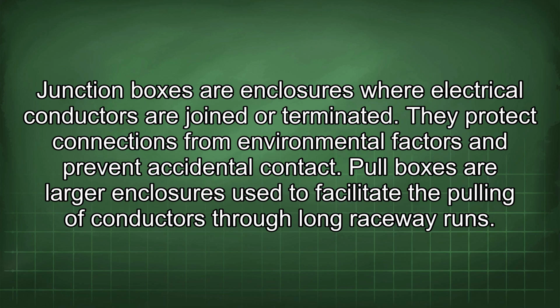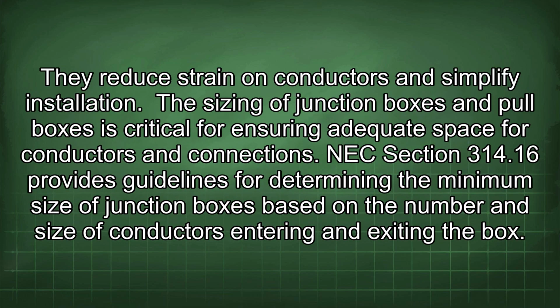Junction boxes are enclosures where electrical conductors are joined or terminated. They protect connections from environmental factors and prevent accidental contact. Pull boxes are larger enclosures used to facilitate the pulling of conductors through long raceway runs. They reduce strain on conductors and simplify installation. The sizing of junction boxes and pull boxes is critical for ensuring adequate space for conductors and connections. NEC Section 314.16 provides guidelines for determining the minimum size of junction boxes based on the number and size of conductors entering and exiting the box.